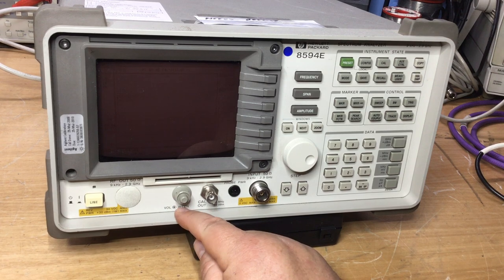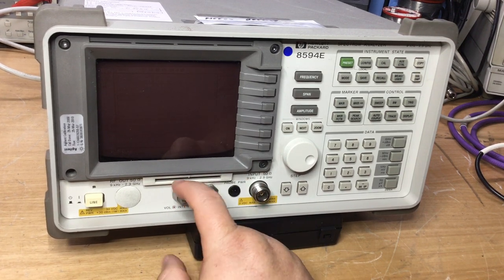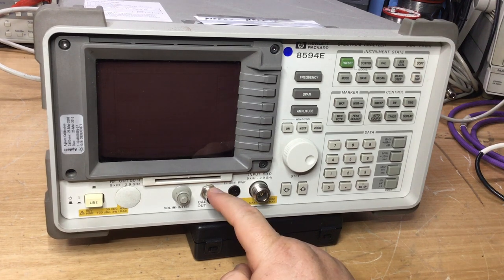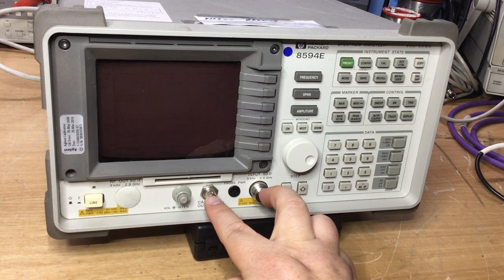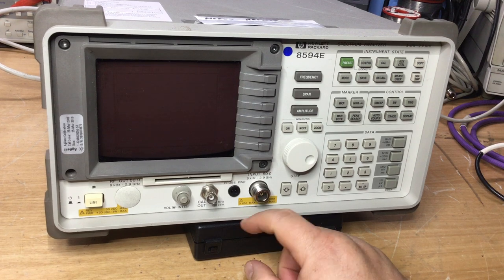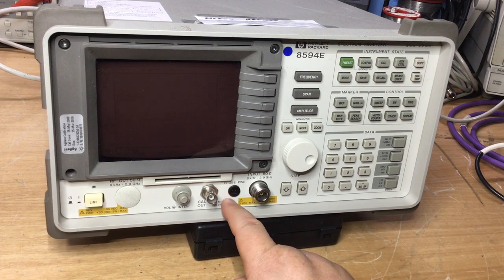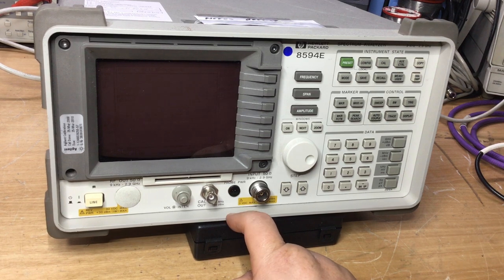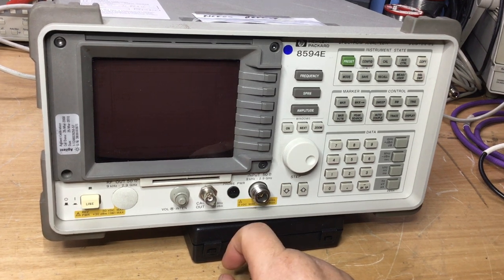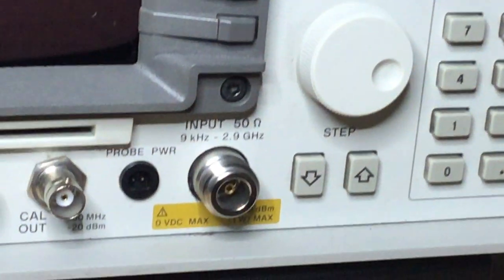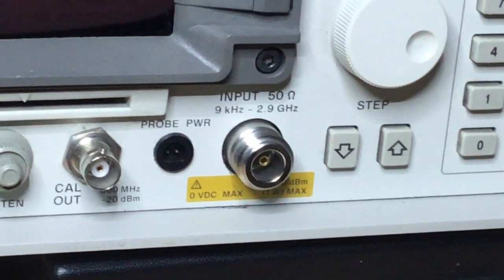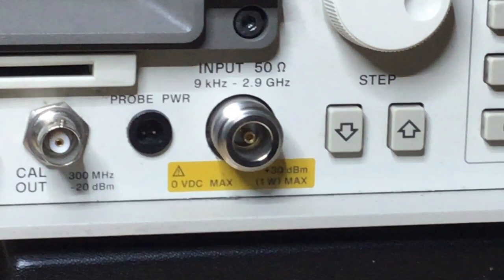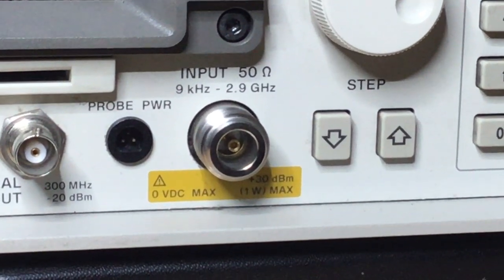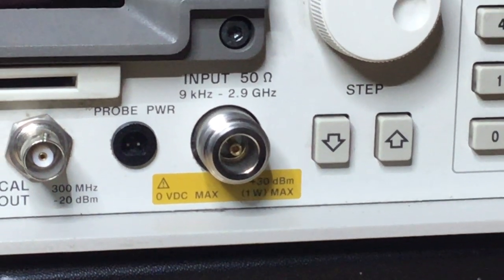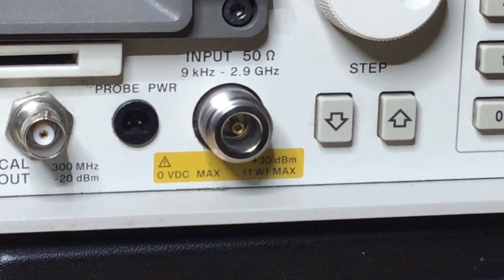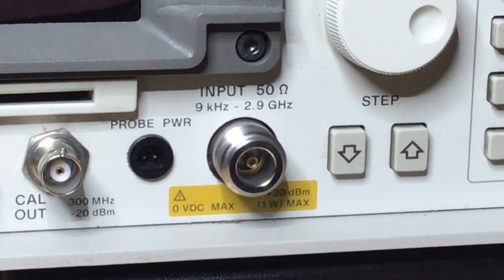On the front here, we've got the volume control and the intensity knob, and the memory card slot. We've got the cal output, which links over to this when we do the calibration. Those two link together. We've got a socket for feeding power to a sensor probe or other accessories that connect in there for HP Agilent. We'll notice as well, when we look at the RF connector on the front, it says a DC level of 0 volts DC maximum and 1 watt maximum RF power, which is plus 30 dBm. That's quite interesting, because it could be that DC bias has been fed up this.